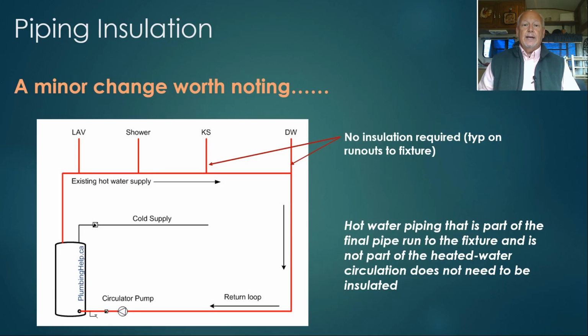This has been modified now, so those runouts, as I've shown here, this is a simple single riser recirculation system. So those runouts to the lavatory, shower, kitchen sink, and dishwasher do not need to be insulated. However, the recirculation system back to the water heater does need to be insulated. So it's a minor change, but it's helpful to get some clarification of what's acceptable.